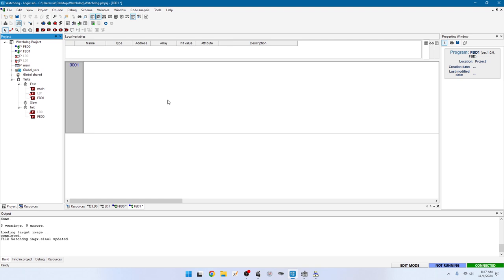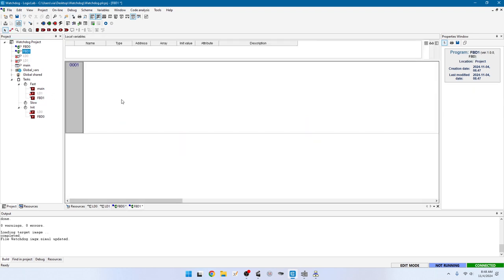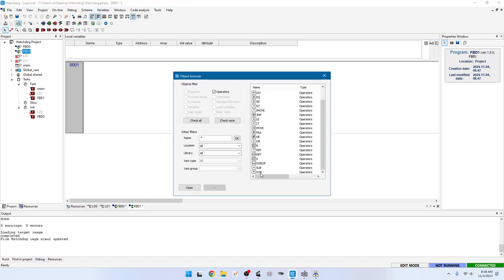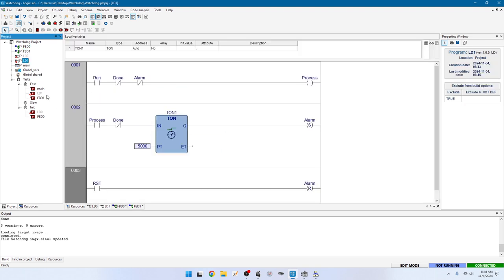Now exclude LD1 and add a new function block diagram program — FBD1 — assigned to the fast task. We want the process to be true if run is true AND done AND alarm are both false. There's a smarter way using DeMorgan's theorem: NOT done AND NOT alarm is the same as NOT of (done OR alarm), which is the NOR of done and alarm. So we can use a NOR operation to save some space.